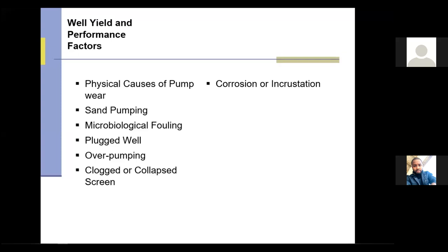Keep in mind, there's a lot of minerals in groundwater, and they could easily adhere to the screen and cause hardness, scaling, and it plugs these wells up. You can overpump. And we talked about overpumping. Think about it like that straw. If you're sucking too hard on that straw, the straw collapses and causes issues. Clogged or collapsed screen causes that. So there's a number of issues here, and you guys as operators should be aware of the different issues.